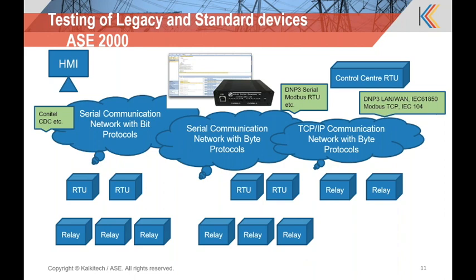With our test set, you can simulate master communications and test outbound requests and evaluate the responses. You can also emulate or simulate an RTU or field device, scan for responses and requests that come downstream, and actually generate those responses back.